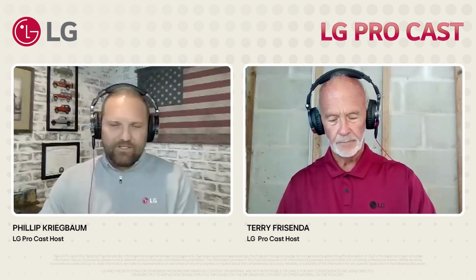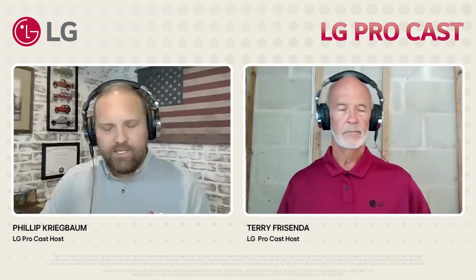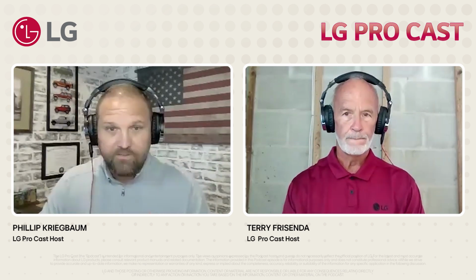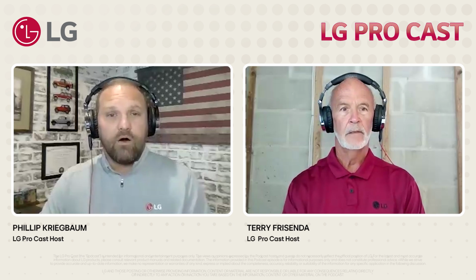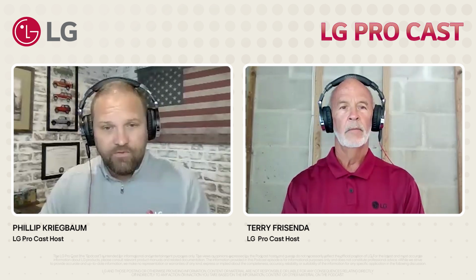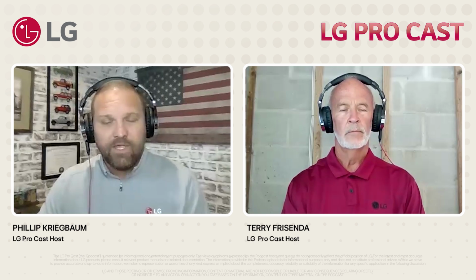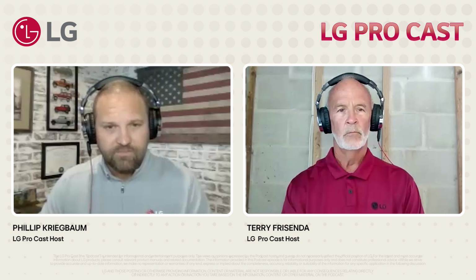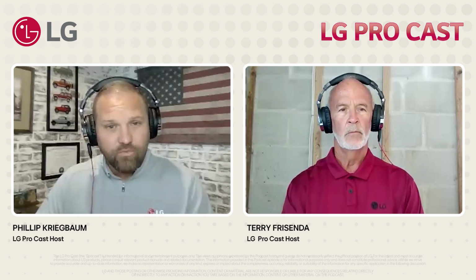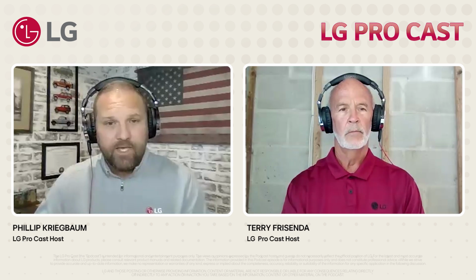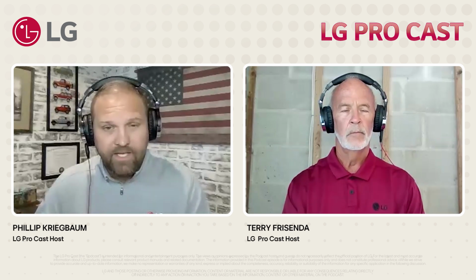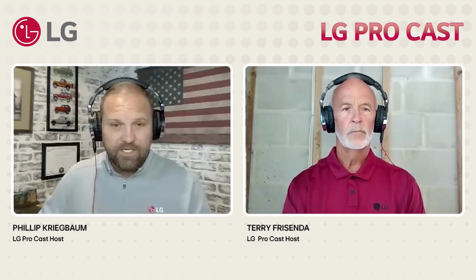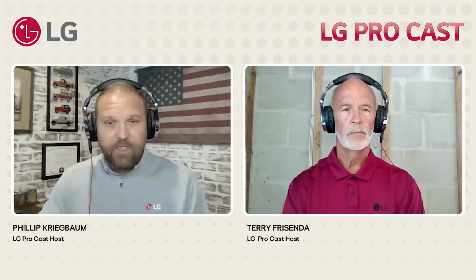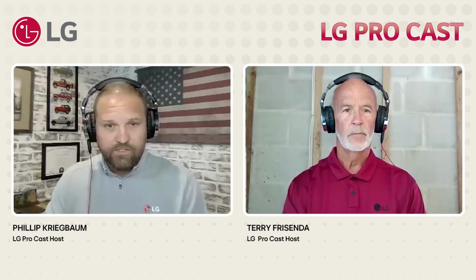Yes, sir. So first of all, I want to point out that this is a bit of a confusing point, and for that I apologize, but it is what it is. We transitioned almost all of our equipment over to 5 wire. There are a handful of units that are going to remain 4 wire, and those are the single zone wall mount systems, single zone only. So that's the Art Cool Premier and Deluxe, that is the extended pipe, and then the Mega and standard efficiency systems. So if it's a single zone only wall mounted system, it's going to remain 4 wire with the 14/4 that we've always used. So that is on the wall mount side, that's going to be the high efficiency. And then everything else that's not a wall mount is all going to 5 wire.